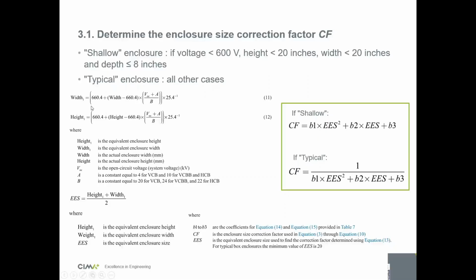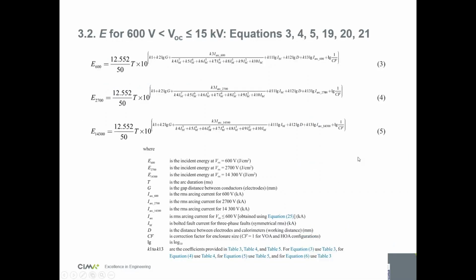So you take your width, you take your height, you take your voltage, and you calculate a few factors here, and then you find the equivalent enclosure size ratio, and then you find your enclosure size correction factor. If it's shallow, it's this formula. If it's typical, it's this formula. Then this is the big equation.